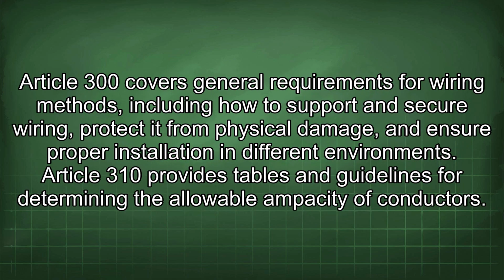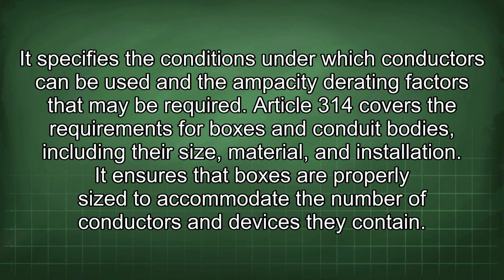Article 300 covers general requirements for wiring methods, including how to support and secure wiring, protect it from physical damage, and ensure proper installation in different environments. Article 310 provides tables and guidelines for determining the allowable ampacity of conductors. It specifies the conditions under which conductors can be used and the ampacity derating factors that may be required. Article 314 covers the requirements for boxes and conduit bodies, including their size, material, and installation. It ensures that boxes are properly sized to accommodate the number of conductors and devices they contain.